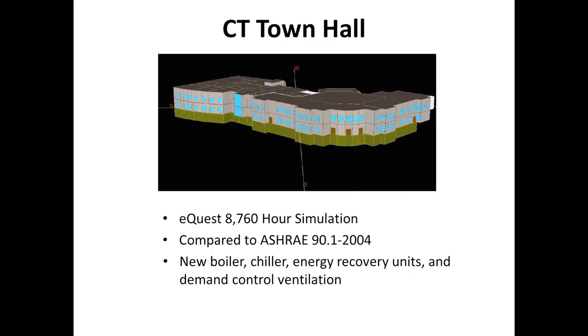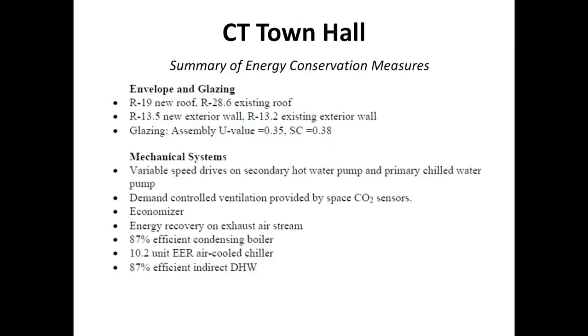The green layer, just visually, is the below-grade levels. We had to add the right amount and size of glazing, meaning windows. Again, eQuest runs 8,760 hours per year, so it's an hourly simulation. ASHRAE Standard 90.1 told us the minimum energy efficiency conditions, and that was the baseline case, as if we replaced all equipment as was. We then compared that to putting in a high-efficiency boiler, a high-efficiency chiller, energy recovery ventilators, and demand-controlled ventilation.